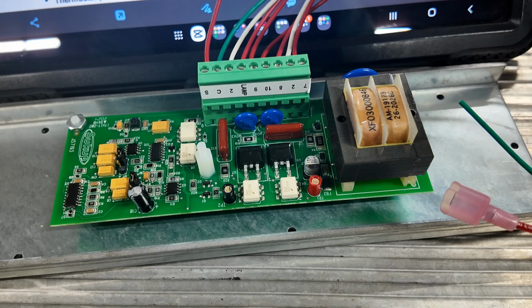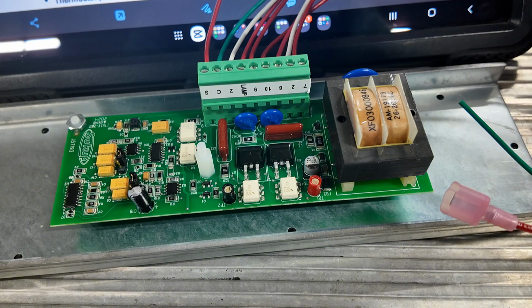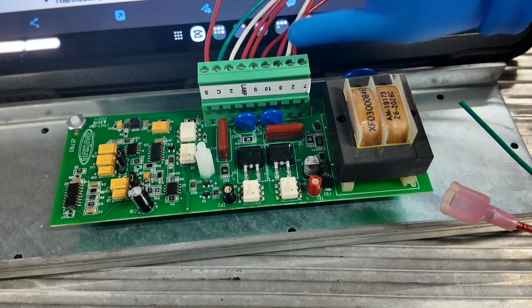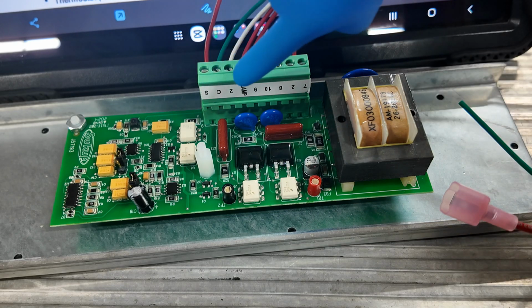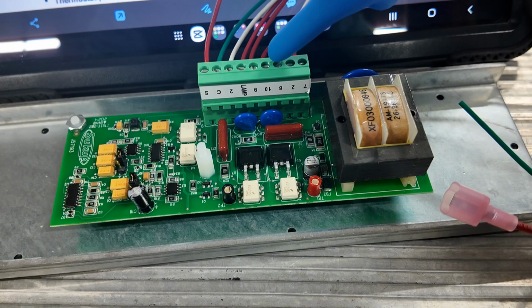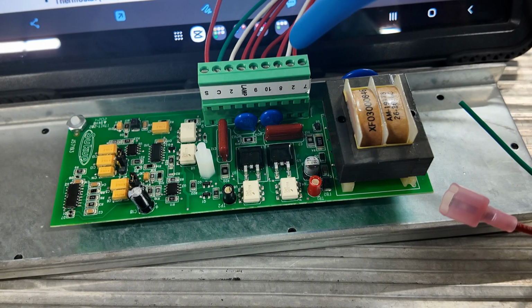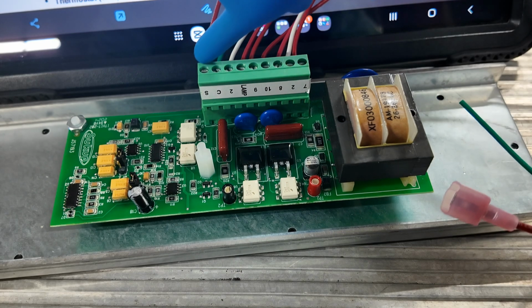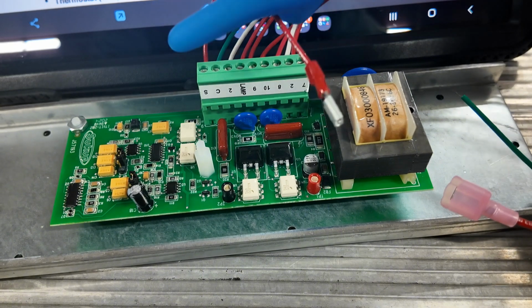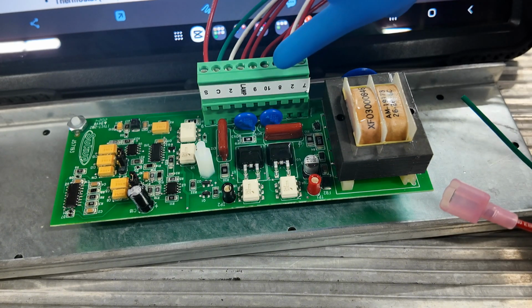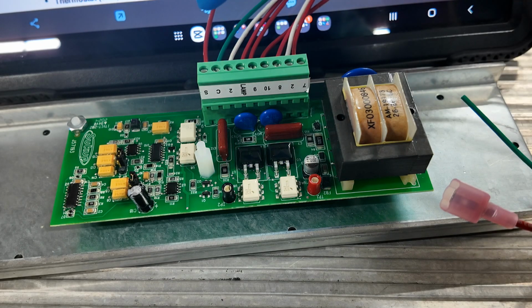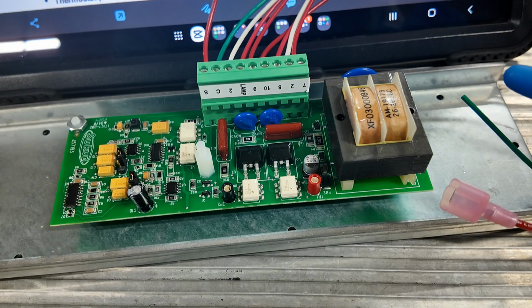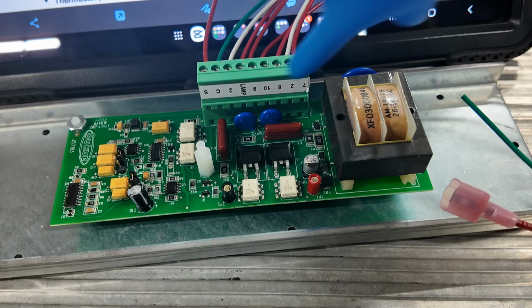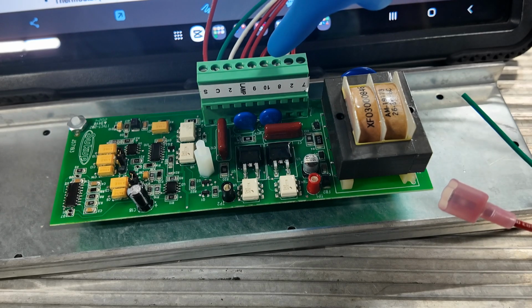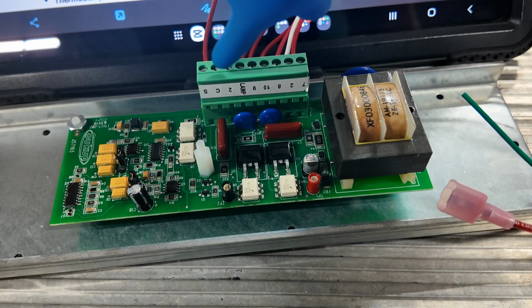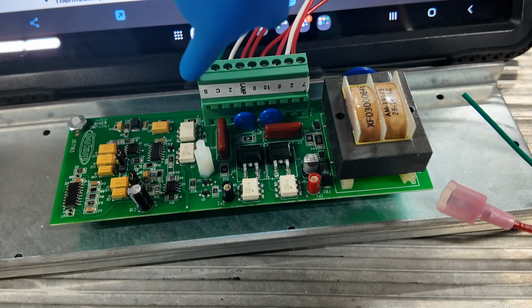If your burner shuts off and all you do is turn the power off and back on, and your burner lights and runs, that is a flame sensing issue. The only thing that turns the burner off with this board is if you take the 110 voltage away from 8 or 7, or if a flame sensing issue. If the S wire, the flame sensor wire, gets shorted out to ground, it will turn off the gas. If it does not sense flame, it will turn off the gas. So if your burner board is turning off the gas while you have 110 voltage on 7 and 8 and neutral on the 2, then you have a flame sense issue.